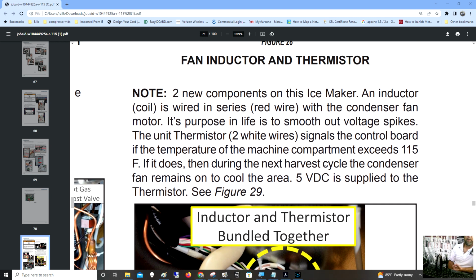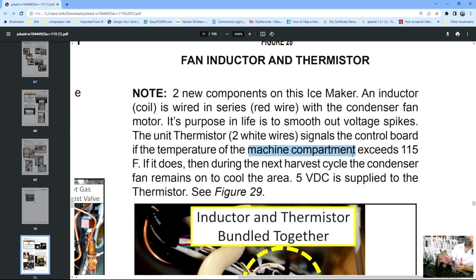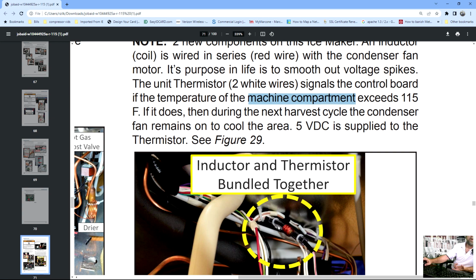The purpose of the thermistor is to measure the temperature of the condensing unit to make sure that we're not overheating the condenser. A lot of people don't service these like the refrigerators. The coils need to be cleaned at least once a year to make sure this thing's going to run efficiently. But if it runs too hot, that thermistor will sense the temperature, and it says here, if the temperature of the machine compartment, and when we're saying machine compartment, we're talking about the compressor condenser area, exceeds 115 degrees, then during the next cycle, the condenser fan remains on to cool the area down. 5 volts DC is supplied to the thermistor.